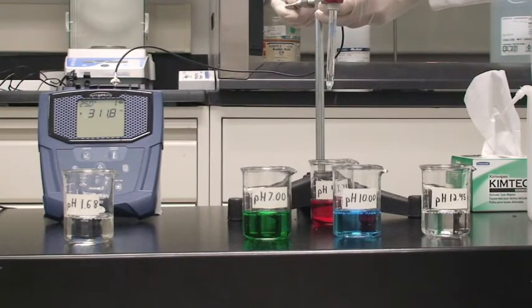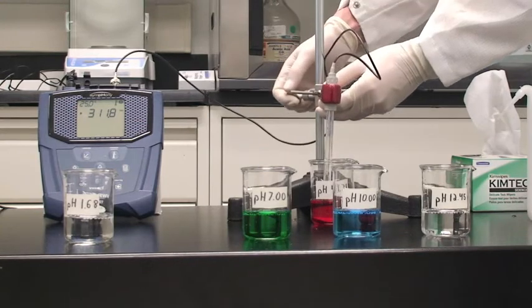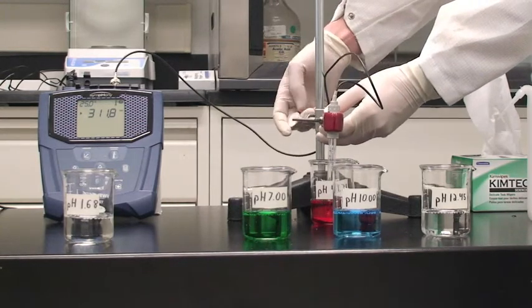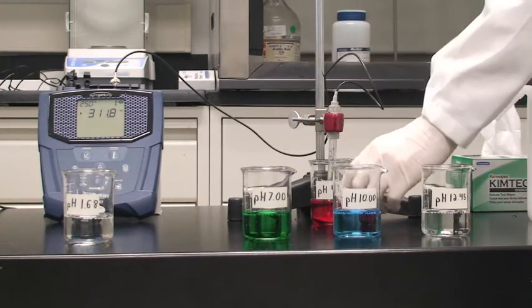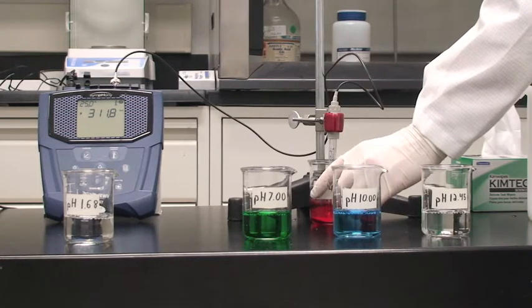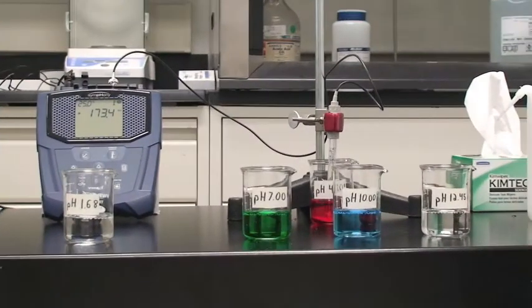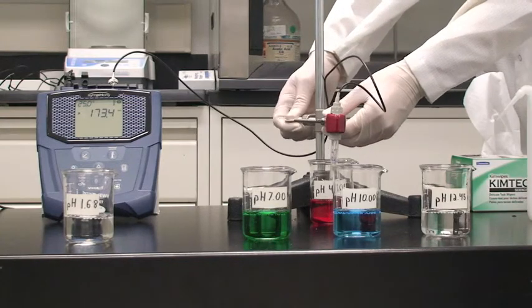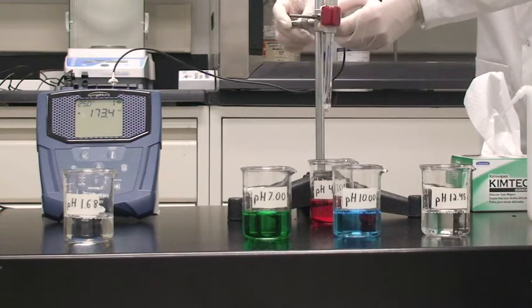A minimum of 3 pH calibration points is required for an accurate measurement. We, however, will use 5 to increase the accuracy of this experiment. Be sure to record both the magnitude and the sign of the cell potential generated. You should expect the potential to change from positive to negative.